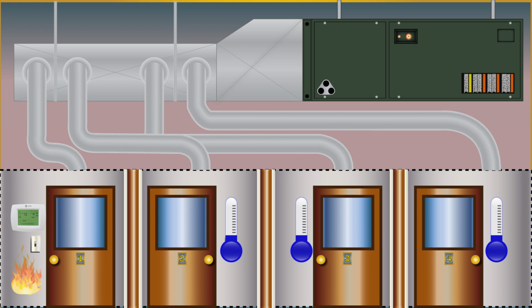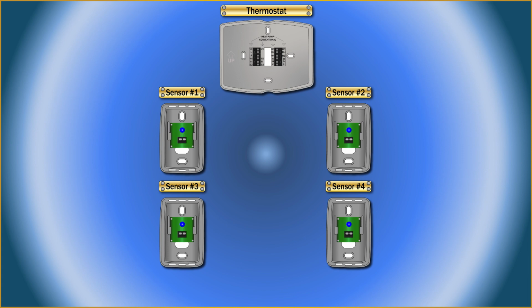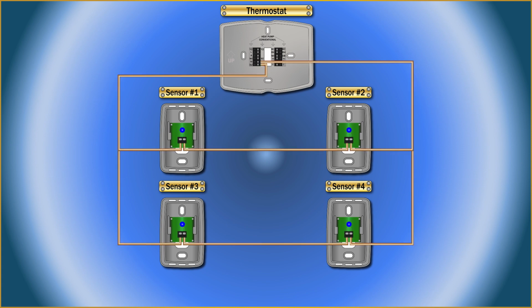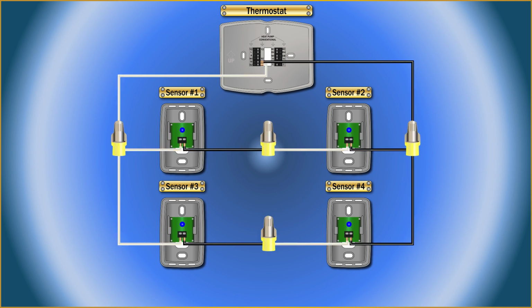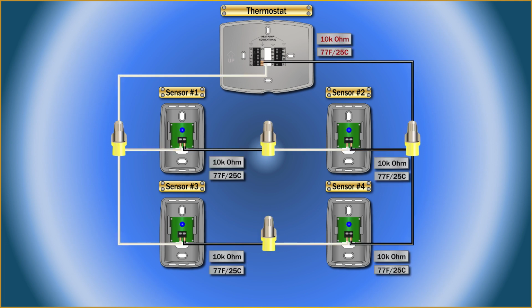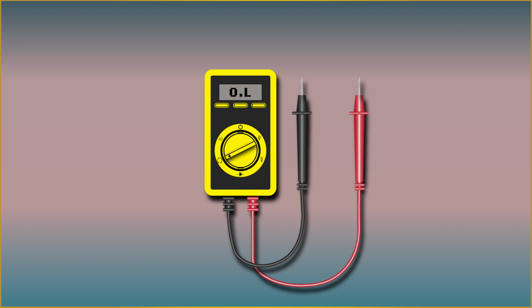So what can we do about this? You can install 4 temperature sensors, one in each of the 4 offices, wire them in series parallel back to the thermostat. The way the voltage travels through the circuit, it comes back as one resistance value, which is the average of the 4 sensors. Pretty cool, right? So what's going on here? Let me explain. When you test a resistor, motor, or other circuit, your meter sends a known voltage out from one of the meter leads through the load or resistor back to the other lead. That voltage then comes back to the meter. The meter can interpret that value and display the corresponding resistance value.